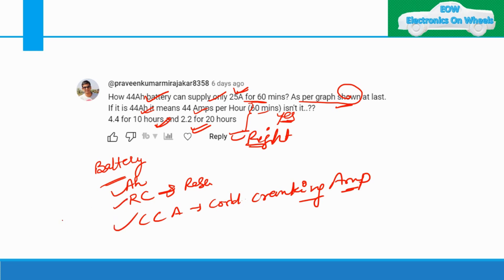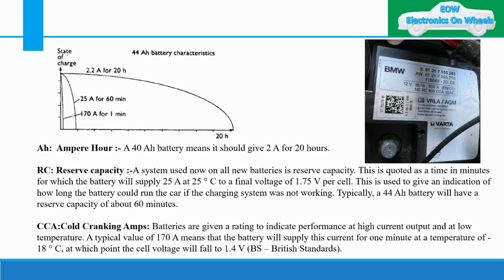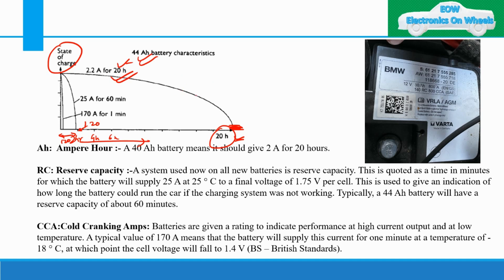Moving to the graph I explained earlier: this shows state of charge versus time. The graph has 10 parts — two hours, four hours, six hours, up to 20 hours. One part represents 120 minutes. So 2.2 amps of current will be provided by a 44 AH battery for 20 hours, draining until state of charge is zero. This is the definition of ampere hours. This is my AH graph.